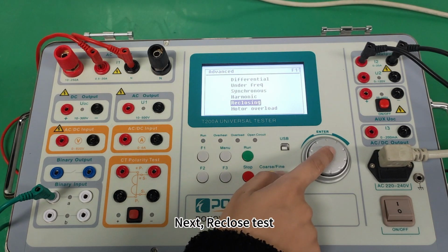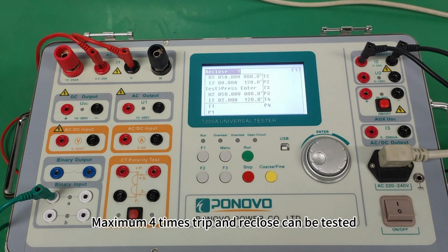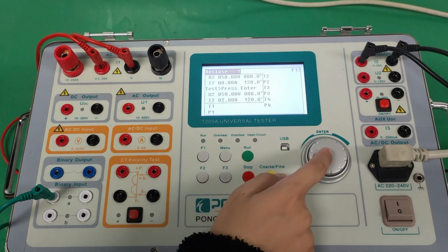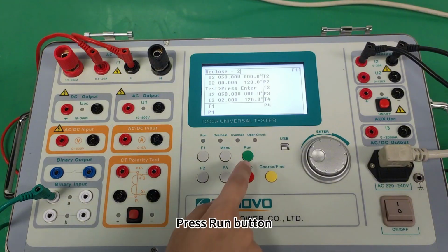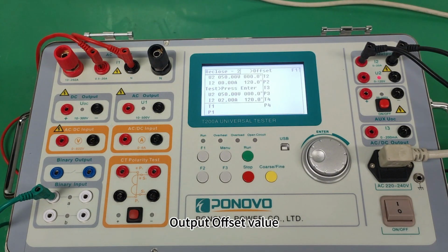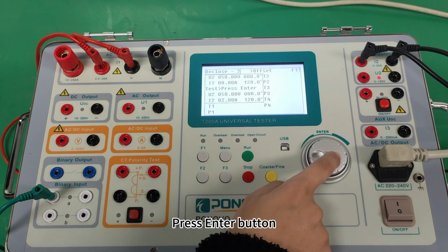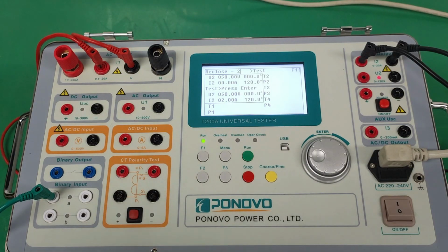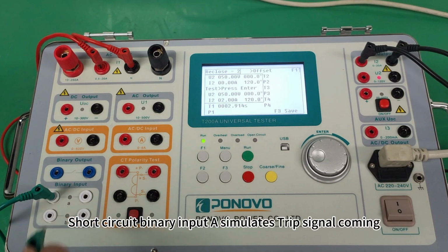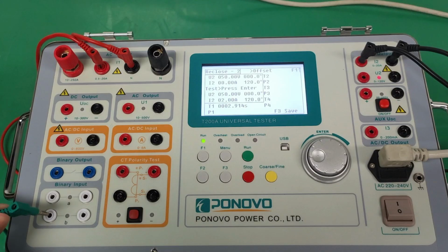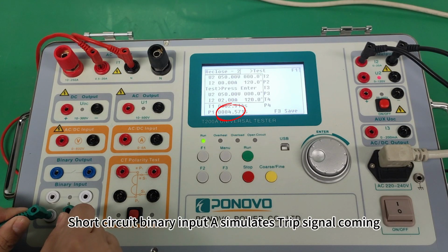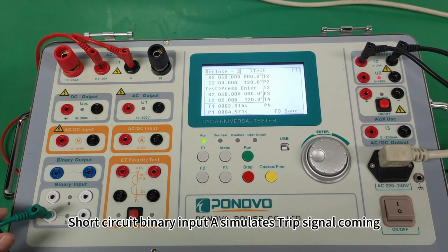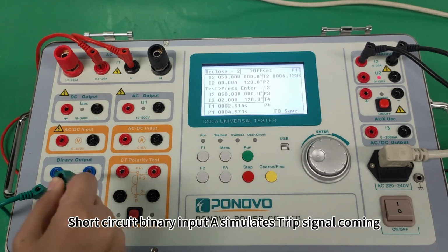Next, reclose test. Maximum 4 times trip and reclose can be tested. Here we set 2 times. Press Run button. Output offset value. Press Enter button. Output test value. Short circuit binary input A simulates trip signal coming. Short circuit binary input B simulates reclosing signal coming. Then secondary trip and reclose.